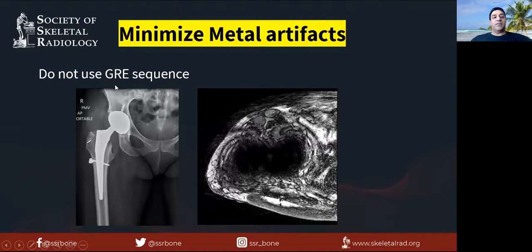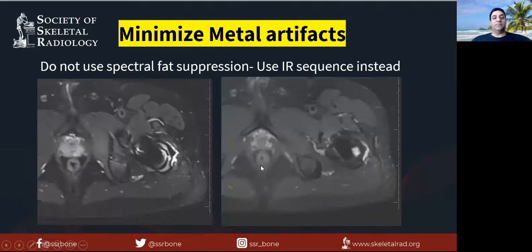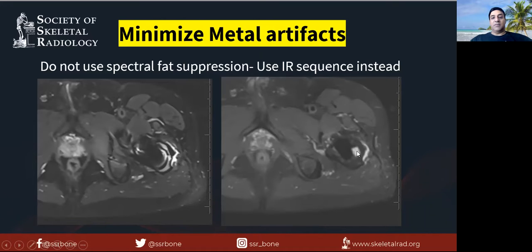To minimize metal artifacts, do not use gradient echo sequences — they're fast but not good. Here you can see a metal prosthesis with a lot of artifact. Do not use spectral fat suppression because you get a lot of artifacts and you can hide areas of particle disease which are better seen on the inversion recovery sequence. Inversion recovery is based on timing, not frequencies, and the frequencies are disturbed while timing is not — so you can use the inversion recovery sequence.